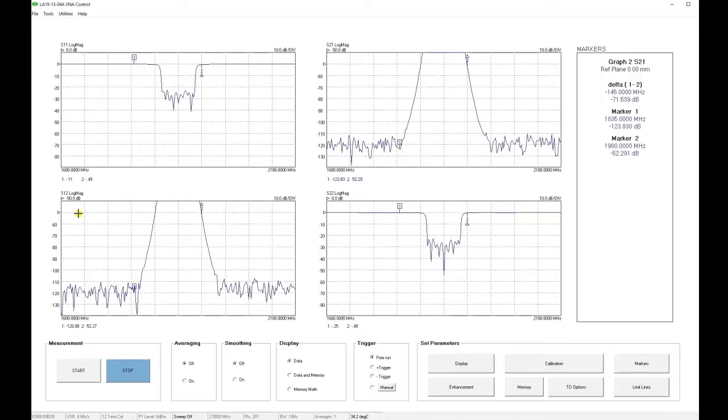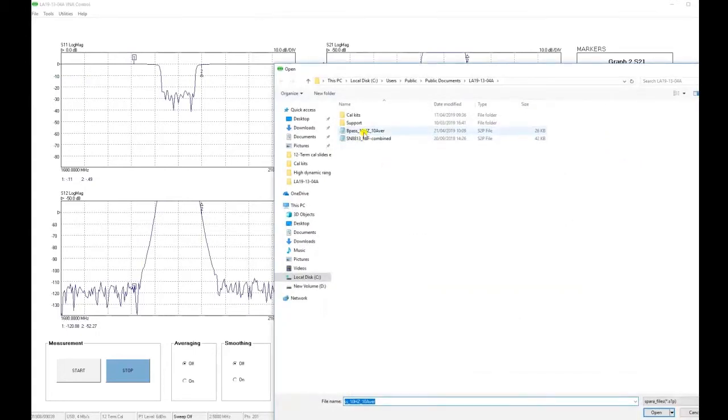Earlier, I repeated the calibration and measurement also using a 10 Hz bandwidth, but with the averaging set to 10, that approximates to reducing the measurement bandwidth from 10 Hz down to 1 Hz. I saved the measurement results to disk, and I will now load those results to the memory so that you can see the difference.